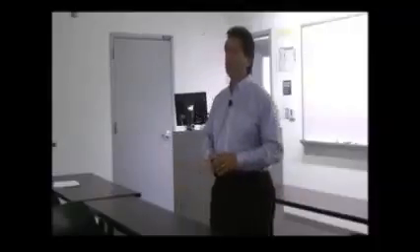It's commissioned, right? Well, part of the commissioning, though, what should you be doing as part of the commissioning cycle? Running it to full heat, right? So then it's like, you know what? It's July. Let's run it to full cool. All of a sudden, December rolls around. So you go down to your thermostat or your energy management system and you crank up the heat. There's no heat. So first thing they do, you go to either the breaker or you go to the fuse box. Okay, up at your reheats. There's nothing there, right? So you plug them in. But again, this is what's considered quality and rework, because now it's going to cost labor to go back and do that. Should have been caught in the first place, right?